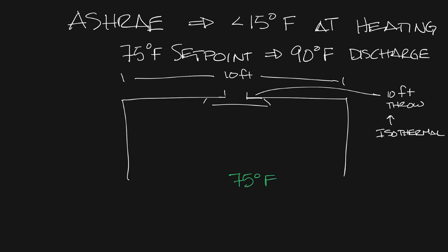So let's say our set point is 75 in the space and we've got 75 degree air for our first condition here. The air in the diffuser is designed so that it comes through the space, rolls across the ceiling, and then down the wall to mix the air from the room into the supply air to make the room comfortable. So this diffuser had a 10 foot throw so it'll go five foot across the ceiling and five foot down.